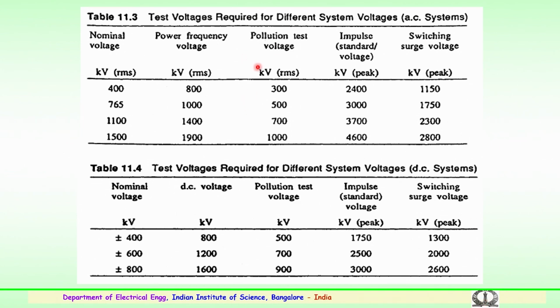Again you see various values. For a nominal operating voltage of 400 kV, the power frequency voltage requirement is 800 kV, pollution is 300, the impulse standard is 2400, and switching surge is 1150. For a 765 kV AC system you require the equipment to be tested for 1000 kV power frequency withstand at 50 hertz, a pollution level of 500 kV, an impulse test voltage of 3 million, or 3000 kV, and 1750 being the switching surge voltage. So, these are some of the values which have been prescribed for both the AC and DC systems. Again for DC 400 kV it is 800, for pollution it is 500 kV, impulse being 1750, 1300 kV, and so forth.